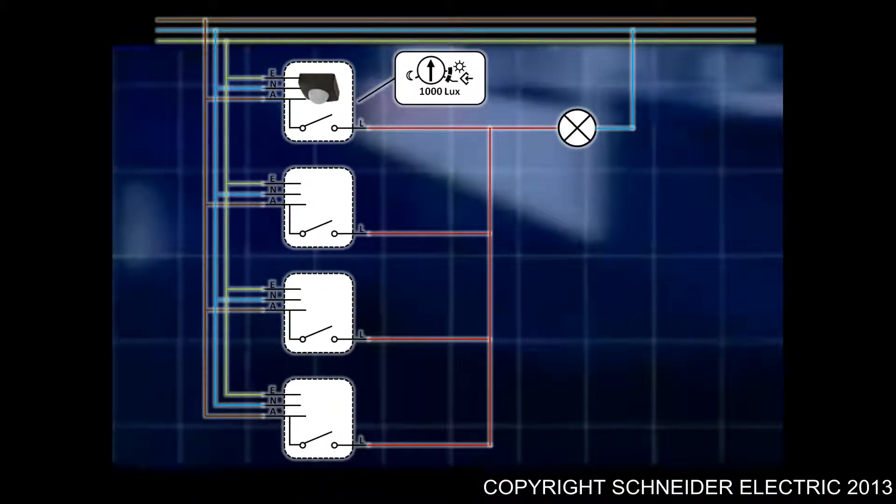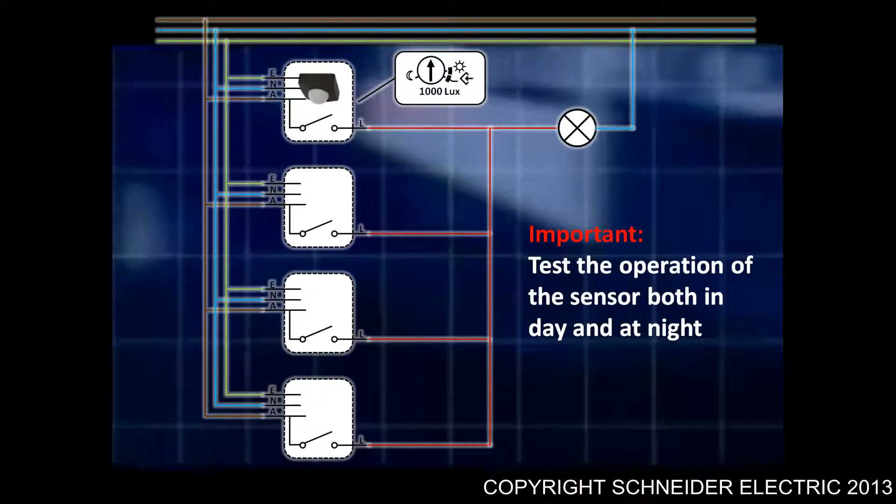When you test it, make sure you do a day test as well as a night test. So for a day test, once you've programmed it, move around underneath it. What you should find is that the sensor shouldn't turn the light on.